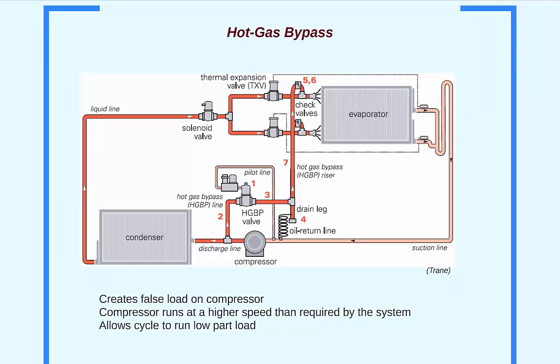Another effective part load design that you may have heard of is hot gas bypass. This requires installation of an additional hot gas bypass valve as well as piping between the high side and low side of the cycle. There are 4 acceptable ways to install hot gas bypass, but the preferred method is shown here. After leaving the compressor, some of the discharge vapor is directed back toward the evaporator and connected between the expansion valve and the evaporator. This creates a false load on the evaporator. The evaporator still extracts heat from the indoors, but this design allows the DX unit to operate at lower part load values. Now you may be thinking, but wait, this is a waste of energy. What sense does it make to increase the pressure and send it right back to the evaporator?